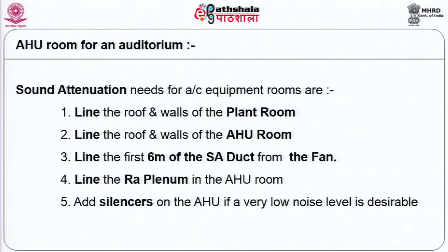One would ideally like to line the floor, but this would lead to a tremendous increase in maintenance, and it is never done. Now, this lining is what is extended to the plant room and the AHU room. In the ducts and all, the same lining is repeated, except that perhaps you do not have an air gap, you just have fibrous material on the wall. These are generally in situ work which is being put in for noise attenuation.